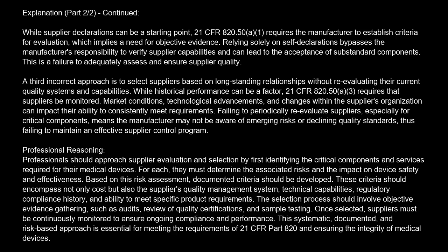Professional reasoning. Professionals should approach supplier evaluation and selection by first identifying the critical components and services required for their medical devices. For each, they must determine the associated risks and the impact on device safety and effectiveness. Based on this risk assessment, documented criteria should be developed. These criteria should encompass not only cost, but also the supplier's quality management system, technical capabilities, regulatory compliance history, and ability to meet specific product requirements.